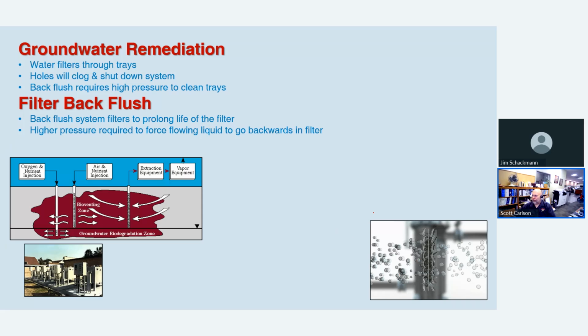With both of these, you have running water. In this case, it's going through a filter, and the particles that it's picking up inside of the filter will start to clog the filter, and you can extend the life of it by using a regen turbine pump to push the fluid backwards, and it'll knock all of these particles out and stir them up so that you can continue using the filter and extend the life of the filter.